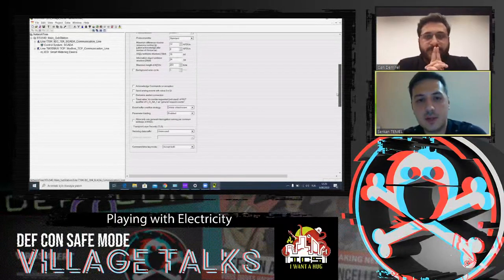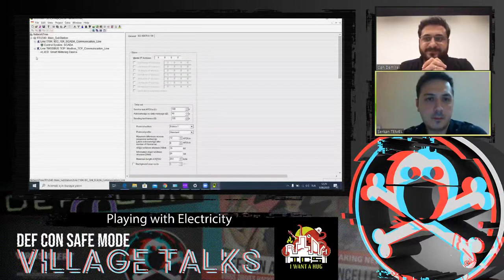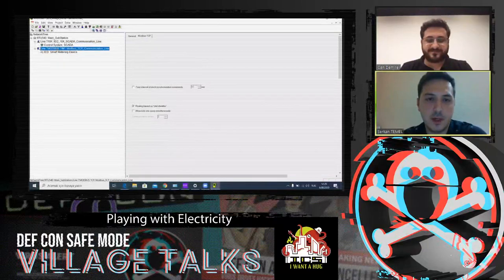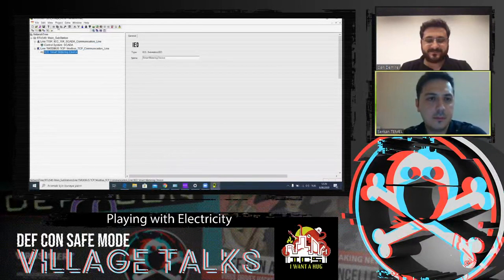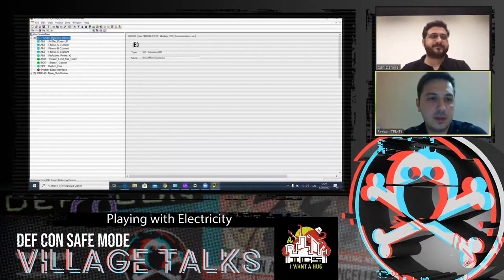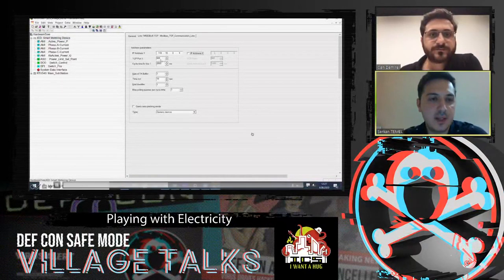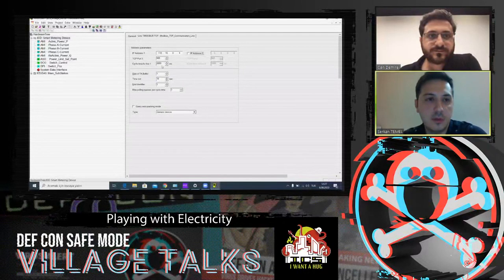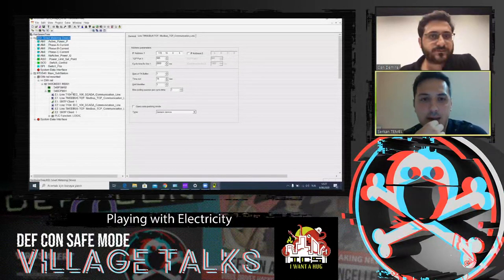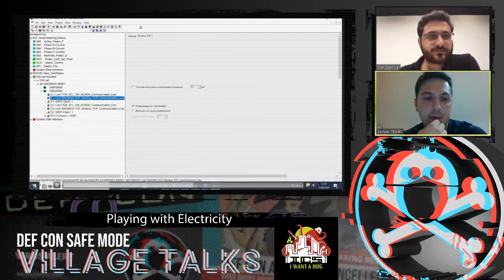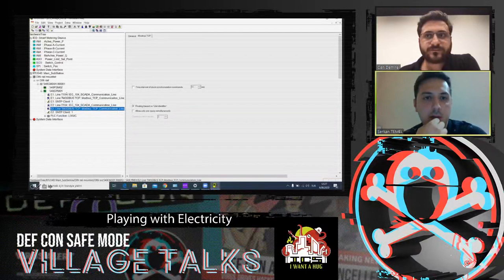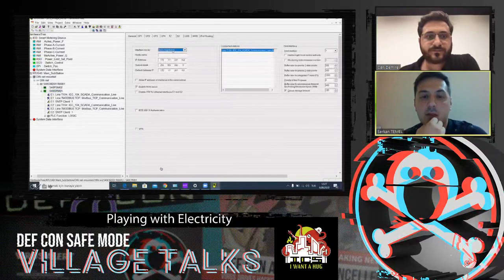As you see, the ASDU address, the address structure, information structure, and maximum length. And this is the Modbus TCP side configuration. This is the network tree. Now we are in the hardware tree. On the hardware side, we choose our RTU main CPU model, and also add the field level signal information. As you see, this is the Modbus TCP communication configuration zone. This is the IP address of the IED device. And again, the 104 configuration section.